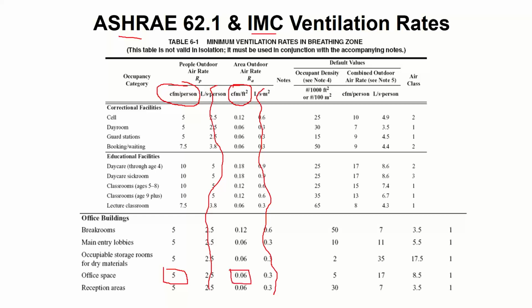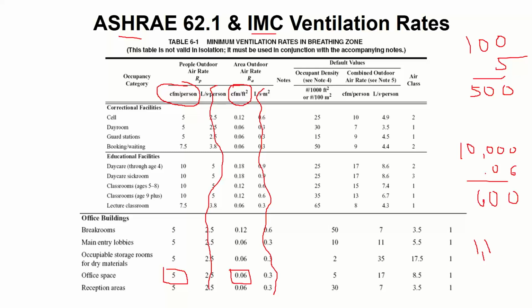square foot. So if I make some easy assumptions here, let's say I have 100 people, right, at 5 CFM per person. For you math wizards out there, that's 500 CFM. CFM is cubic feet per minute, the volume of air. And then I'll also make my life easy and say I have 10,000 square feet for those 100 people. Well, 10,000 square feet times 0.06 comes out to 600. So that means I need a grand total of 1,100 CFM of fresh outside air coming into this space.